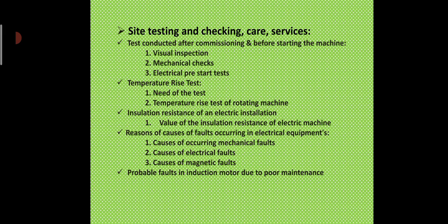In the first case, the whole load is removed from the circuit. All the switches except the main switch are kept closed. Fuse and neutral links are removed. Phase and neutral wires are connected to the megger and the handle of the megger is rotated. The reading of the megger is taken and noted. The reading should not be less than 5 megaohm. If it is less than this value, it shows there is some fault in the wiring. This fault should be detected and measures taken to rectify it so that the insulation resistance does not come out to be less than 5 megaohm.